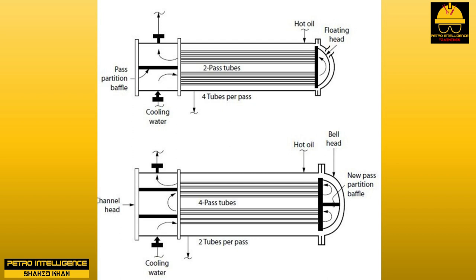The method of calculation to derive the lower flow is somewhat complex; the calculations take into account that the water has to flow twice as far through the tube bundle and that there are only half the number of tubes available per pass, but that the water pressure drop must remain constant. Due to the lower flow, the temperature increases of the sea water also went up: two-pass 70 to 100°F, four-pass 70 to 150°F. At 150°F, the cooling water precipitated hardness deposits, which restricted water flow.